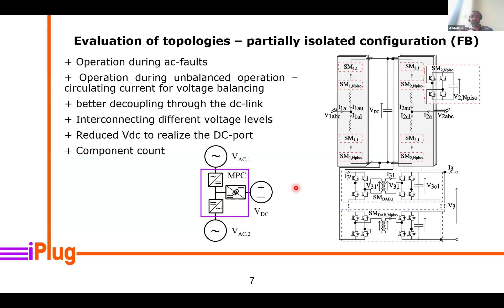As a summary, from the three configurations we've seen, there are two topologies we can compare. One has the typical characteristic of a low number of components; the other has good operational conditions. We optimize this hybrid solution with an isolated DC-DC stage to realize the low voltage DC, but by choosing a DC voltage level lower than what we'd use with half-bridge cells, we can compensate for the component count difference. If we design the converter so the component numbers are similar, the only differentiator is operational complexity and flexibility for different operations.